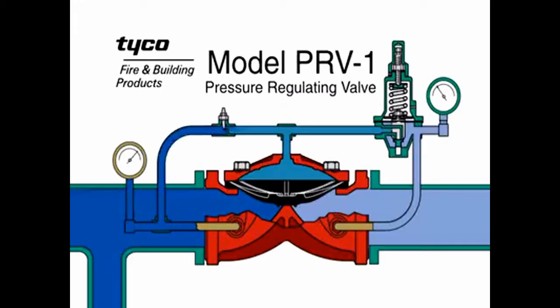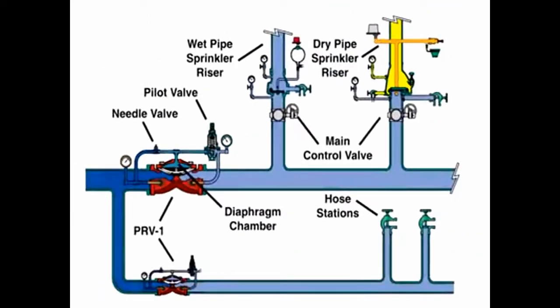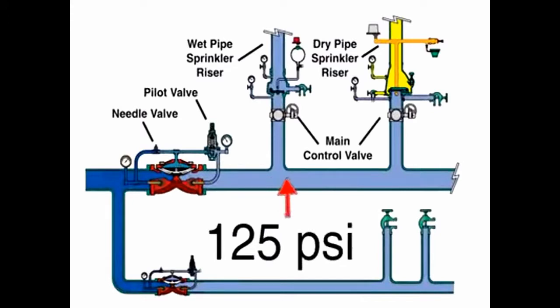The model PRV1 is a pressure regulating valve. The valve is shipped fully trimmed and ready to install. The PRV1 outlet is factory set to a pressure of 125 PSI.